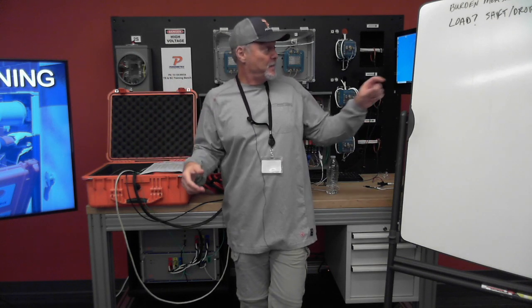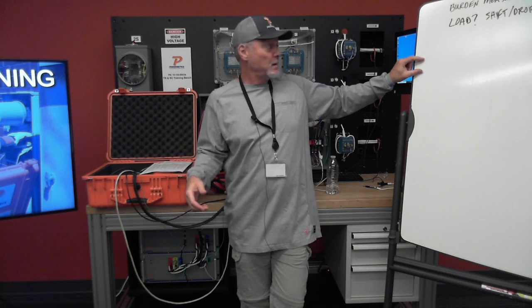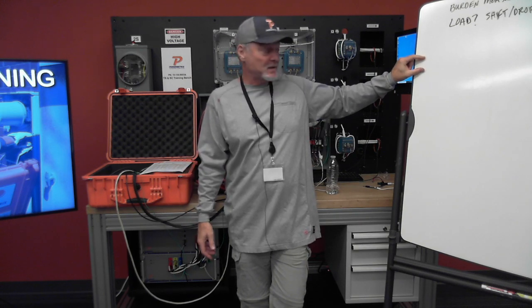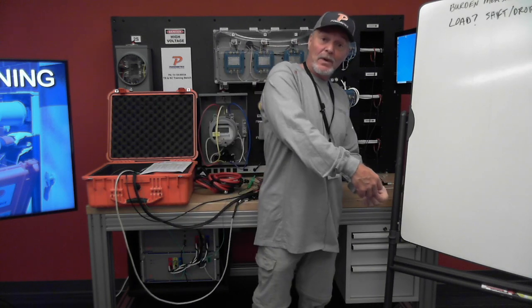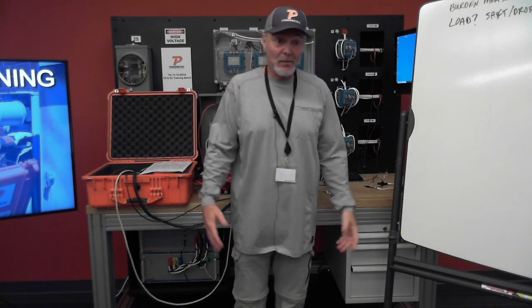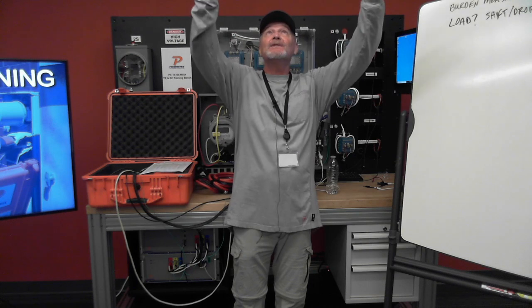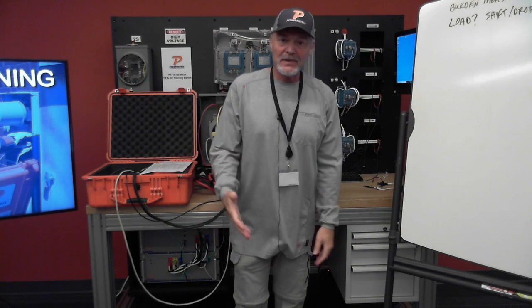You know, the pickup's not on there correctly - my pulse pickup, that's why I'm not getting pulses - versus it's not connected very well at the machine. Versus, instead of saying we got cross phasing on here, let's get a crew out here and change this whole installation out, let's look at something simpler first.